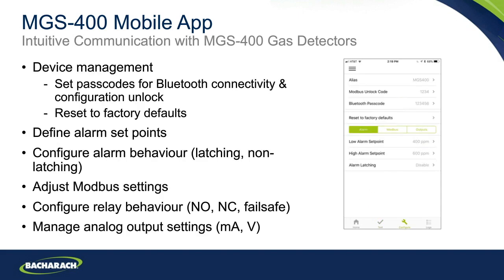But probably one of the key things here is the ease of device management and configurability. The alarm set points here are defined via a simple entry of a number, no calculations on voltages, no adjustments of potentiometers, no restrictions of using dip switches. Everything in here is just a simple, intuitive entry. We also have the alarm behavior configurable as to whether it should be latching, as we discussed is needed for machinery rooms, or non-latching. Modbus settings can be adjusted in here to ensure interaction with any control devices. Relay behavior in terms of normally open, normally closed, fail-safe. This can all be configured here within the system.